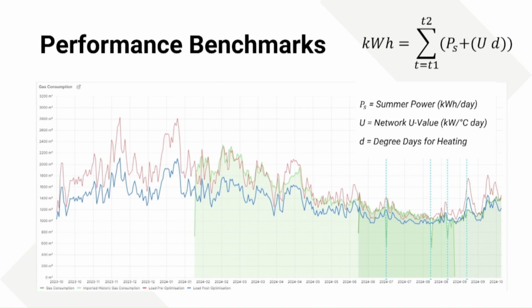This graph shows a live site of 1,000 properties. The green is historic gas consumption. The red and blue lines are effectively before and after optimization curves. You can see how the green tracks the red line before - that gives us our P&U values before optimization, and after optimization we're on the blue curve. So it's a methodology for pinning down the efficiency of a heat network so you can predict the load given any weather conditions. If things don't match these curves, the alarms go off. Every site should match a curve, and if it doesn't, there's a reason. It allows you to keep track, for any given weather conditions, of whether the actual efficiency of the site is going up or down. So that's quite a key one - benchmarking.